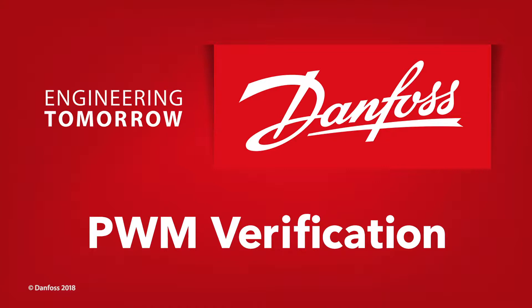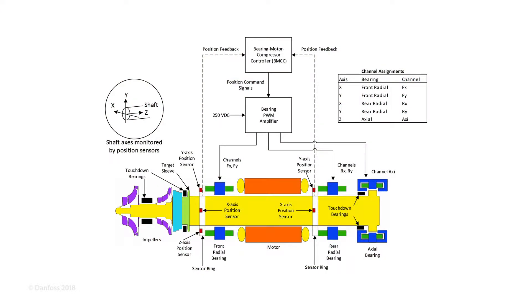As an integral part of the magnetic bearing control system, the PWM amplifier provides power to the electromagnetic bearing coils in response to commands from the BMCC. Additionally, the PWM passes feedback from the bearing current sensors to the BMCC.